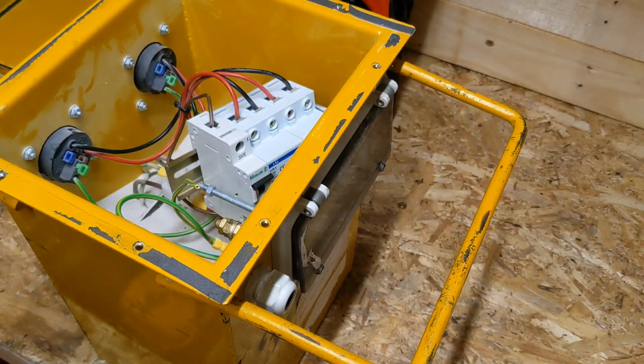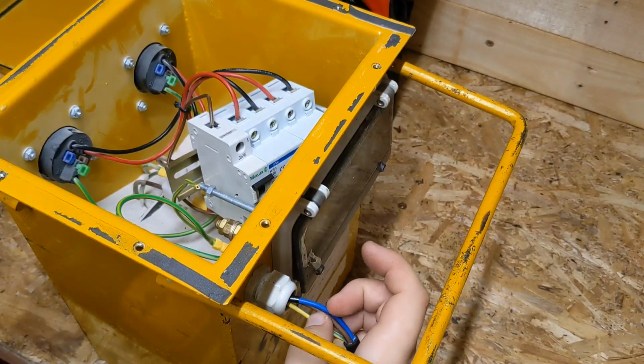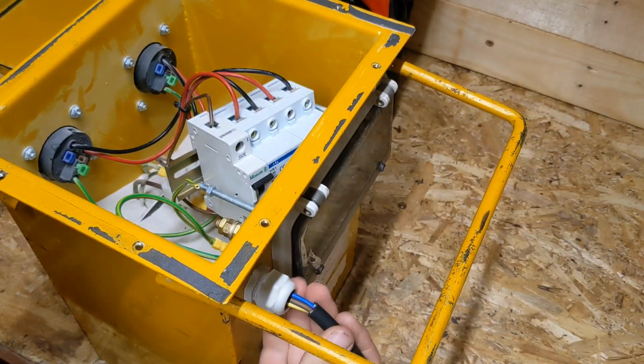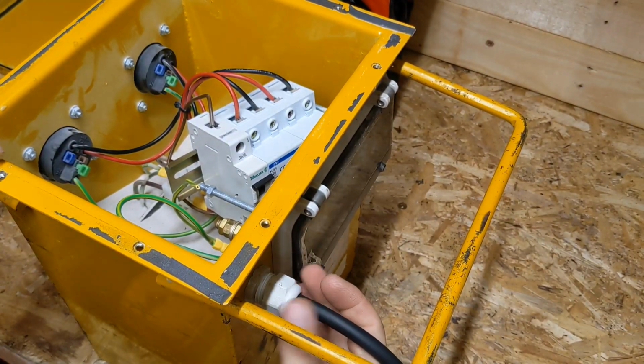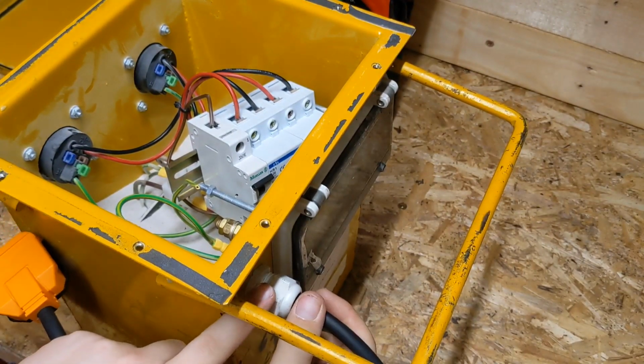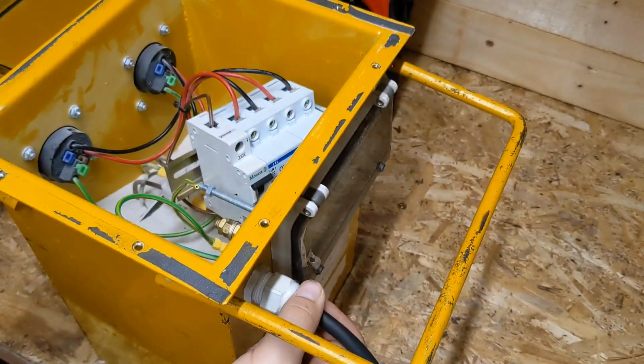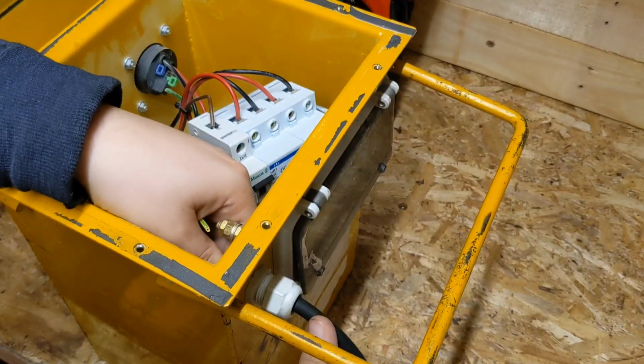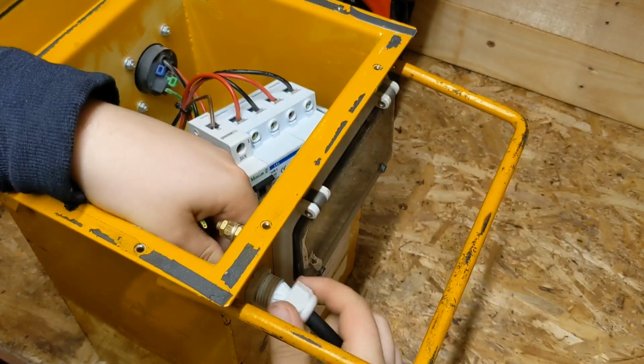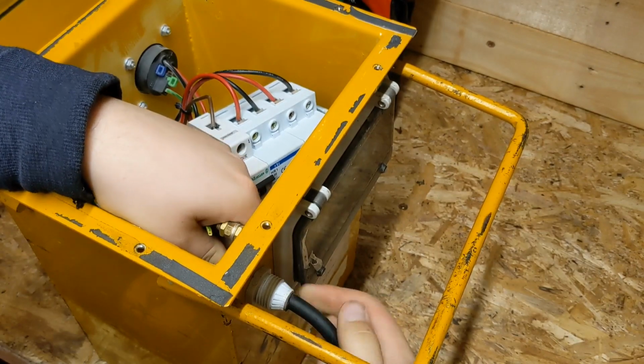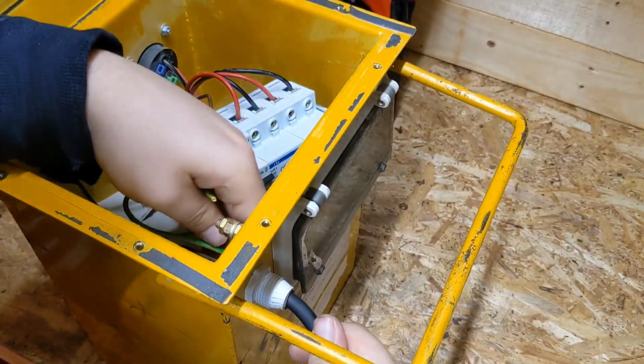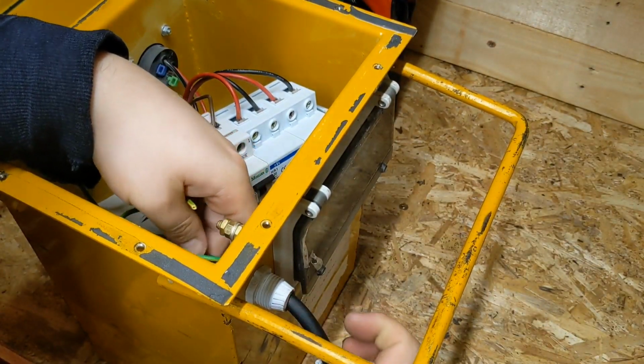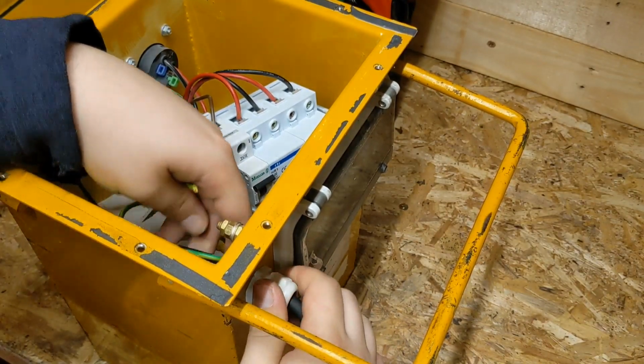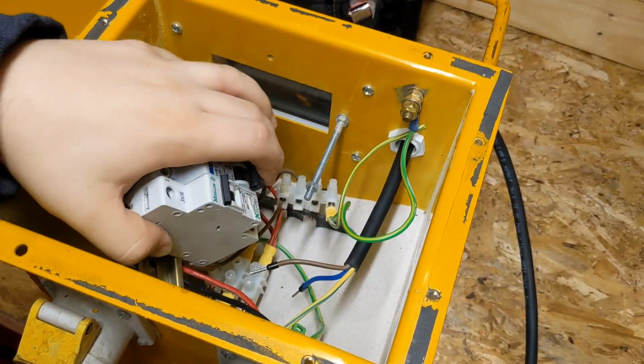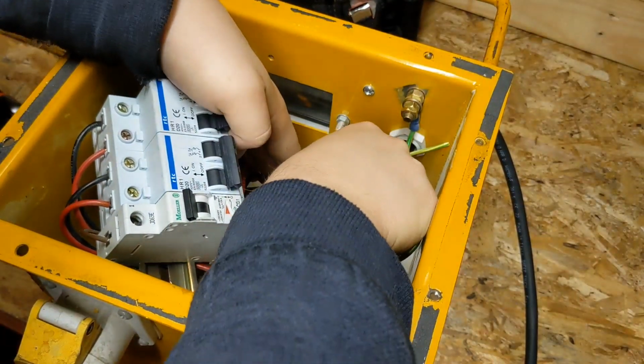Right, so very simply, we'll get the end of our wire, we'll push it through the stuffing gland. Normally on the smaller transformers, the stuffing gland will be on the inside, simply to stop you smashing it off when you bash it against something, but this one's got a metal handle to protect it. So put that through like so, tighten that up, put wires back into the terminal block like so.